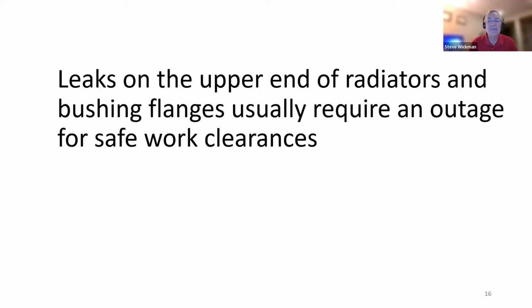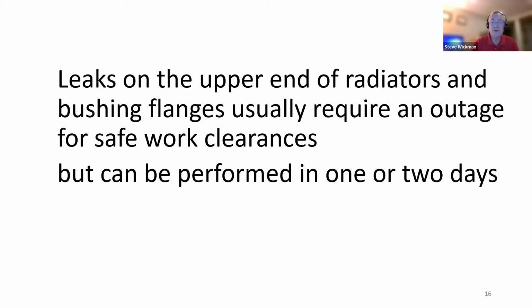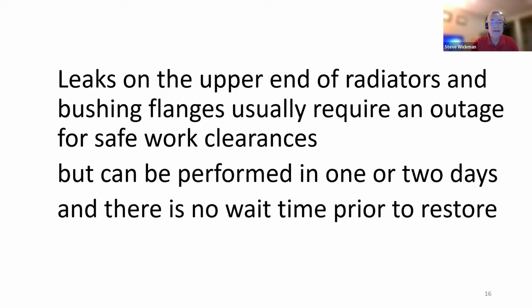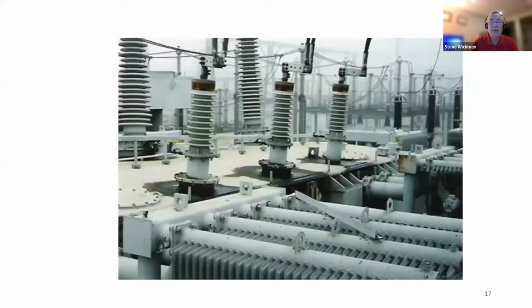And just to highlight, leaks on the upper end of radiators and the bushing flanges usually require an outage, primarily for safe work clearances for the individuals performing the work. But again, it can be performed in just a couple of days, and there's really no wait time prior to restore. Although we do like to leave the unit out of service overnight, just to make sure everything's cured up and we don't have to go back and reshoot something, which would require another outage. So you saw this picture earlier, but just to highlight, to make these repairs on those bushing turrets, and also if we were going to do the drill and inject into the flanges on those top radiators, or some of the other piping on this transformer, we would need to get an outage for safe work clearance from the energized conductors that are above the heads of the technicians doing the work.